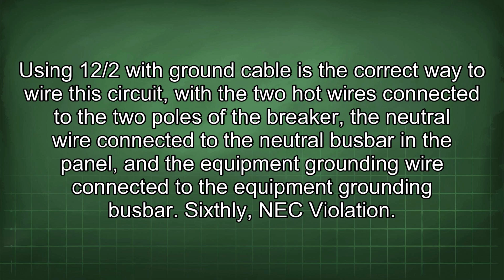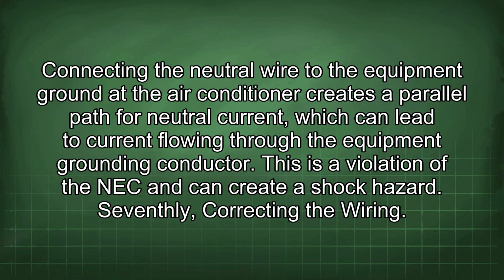Sixthly, NEC violation. Connecting the neutral wire to the equipment ground at the air conditioner creates a parallel path for neutral current, which can lead to current flowing through the equipment grounding conductor. This is a violation of the NEC and can create a shock hazard.